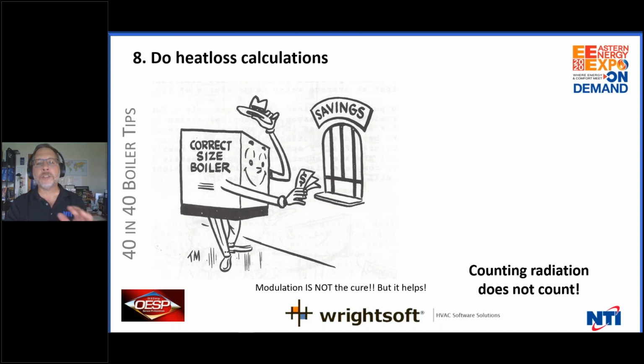And you know, when we got all done doing all these extreme and exact, what we thought were exact calculations, we still added 20 to 30% infiltration and 30 or 40% for safety. All your boilers out there are more than twice the size they need to be. Hell, in my area, we only have to design to 14 degrees. I used to design to 0, adding another 20% onto my boilers. This is huge. Please do a heat loss.